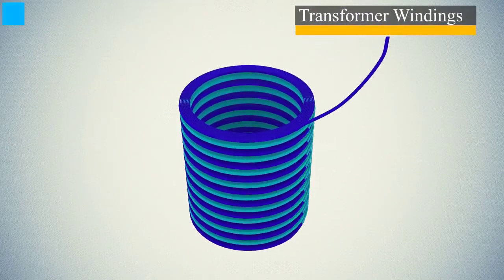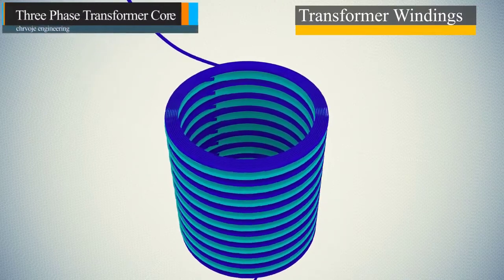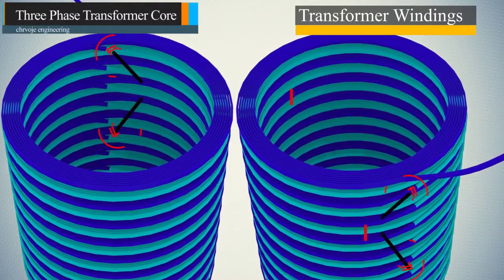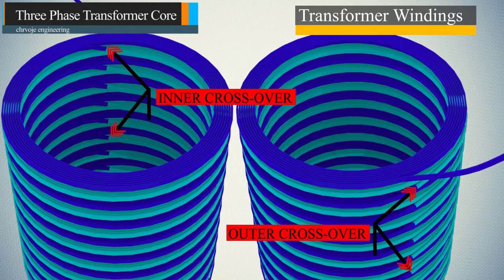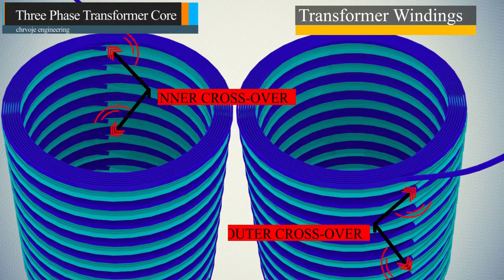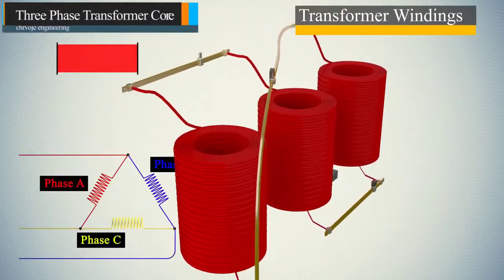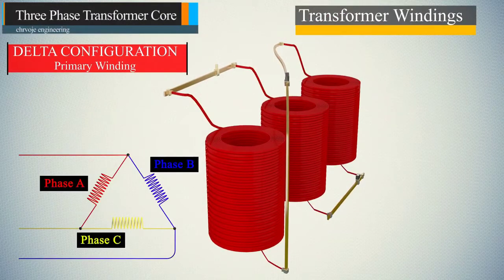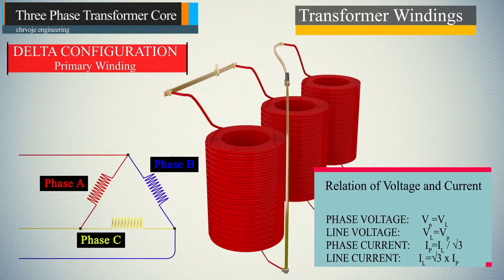It's good to know that disc-type windings are primarily used for high-capacity transformers, like this one. Disc-type windings are made of concentric discs connected in series using inner and outer crossovers. Primary windings, in this case high-voltage windings, are connected in a delta configuration. The delta configuration has the 3 phases connected like in a triangle, and delta configuration is formed by connecting one end of winding to the starting end of other, and connections are continued to form a closed loop. 3 phases are taken out from the coil joints. Voltage and current of delta configuration are given by this relations.